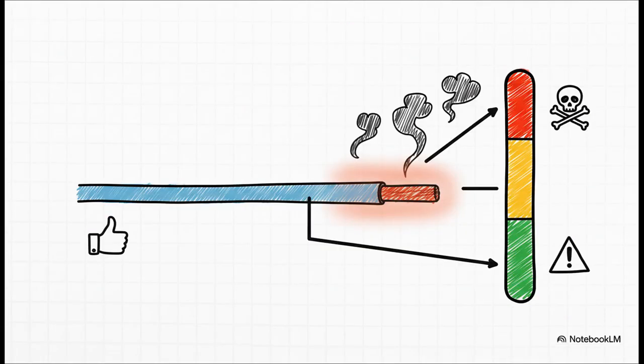So if we look at a typical power cable, for example, its thermal limits break down into 3 zones. You've got ampacity, which is just its normal, safe operating current. Then there's an emergency overload zone, where it can handle a bit more for a short time. But then there's the short circuit damage zone. That's the red line. That's the point of no return. If a fault pushes that cable into this region, it starts to physically break down.